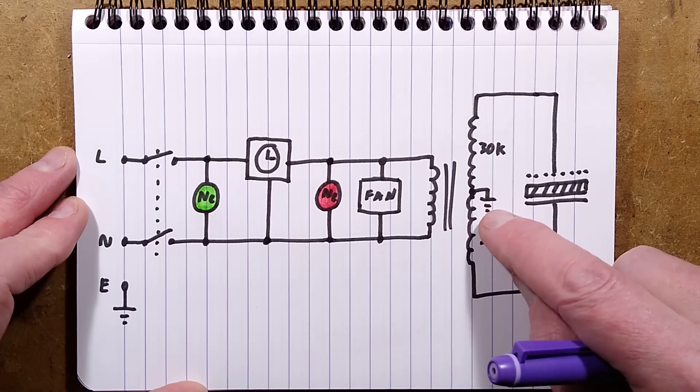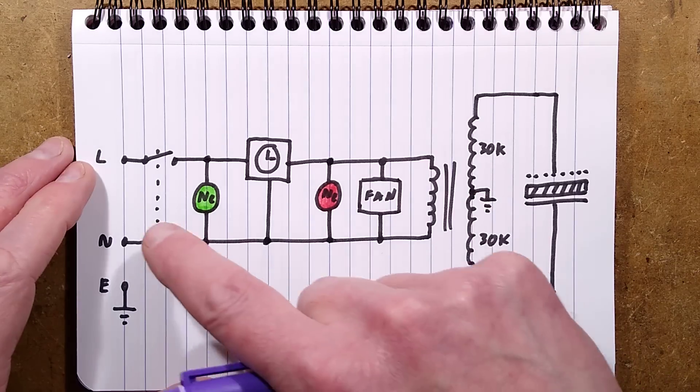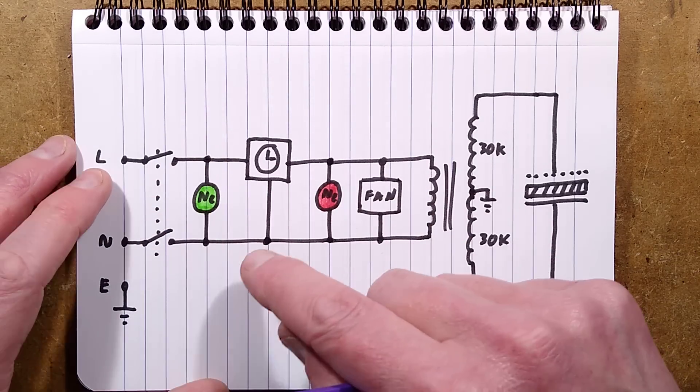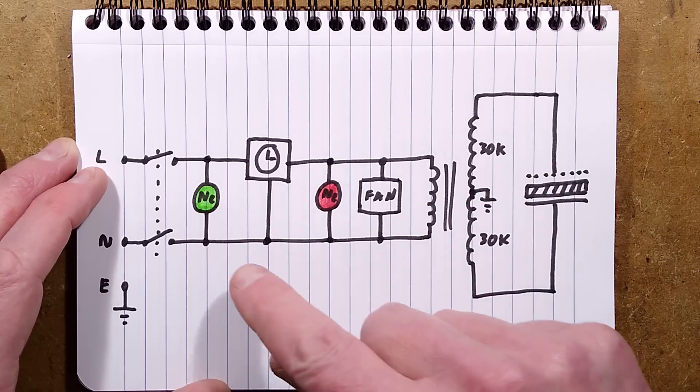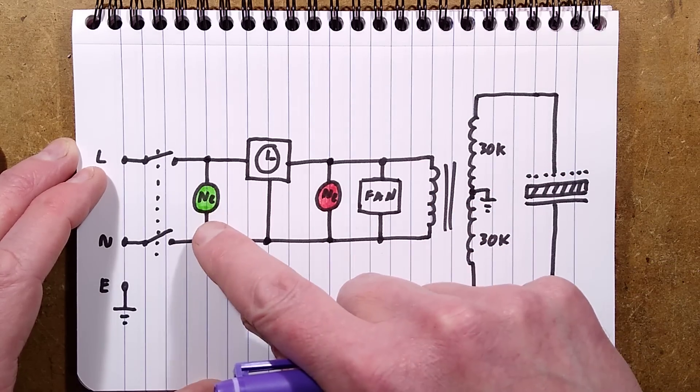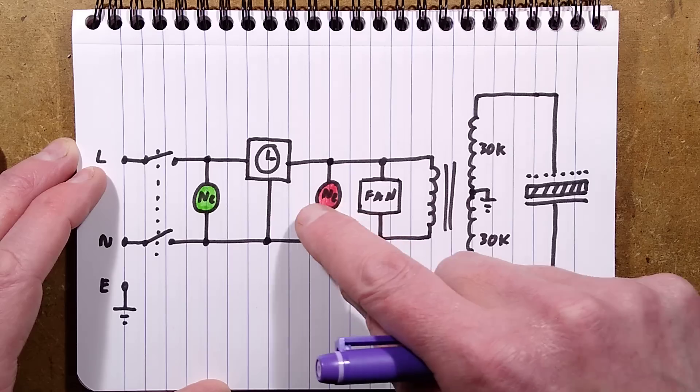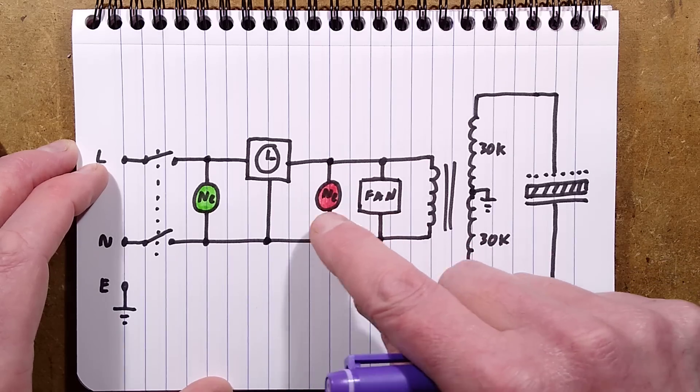So we've got the live and neutral coming in here and the earth for the chassis, but also a center tap earth for the transformer. It goes through an isolator for safety. That's interlock the lid, so the only way you can open the lid is to turn it off before you can open it. We've got a green neon indicator, the time switch, and then a red neon indicator to show that the unit's active.